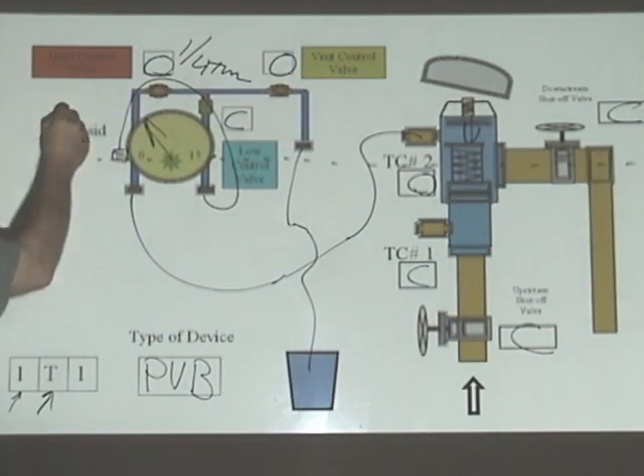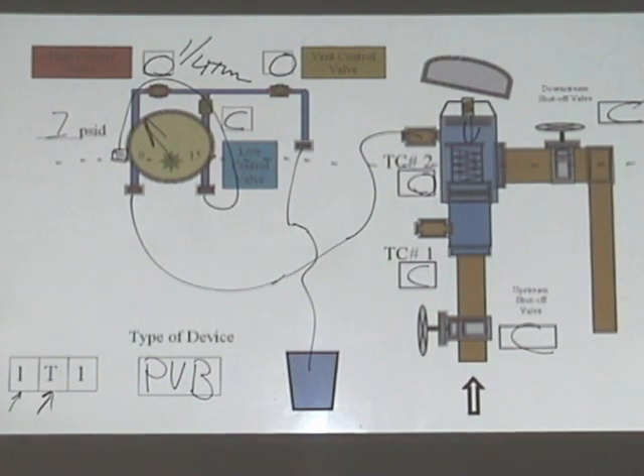You will hear a pop. The air inlet valve will drop down. You'll observe your reading, and it should have all happened before that reached one. That's how to test the pressure vacuum breaker.